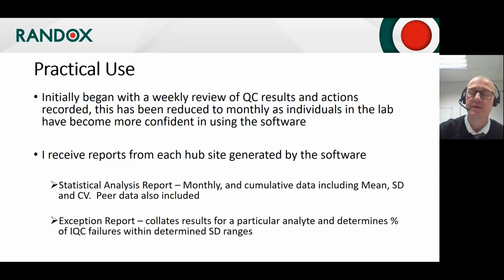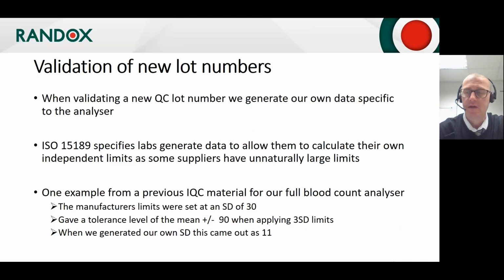I found that this has worked well across all sites, as it does instigate people to look a bit more closely at why they might be getting so many failed QC results, and if there are things that can be put in place to try and minimize it. So when we get a new QC lot number, we generate our own data specific to each analyzer. This data then allows for any inherent biases and errors that are applicable to that individual system.